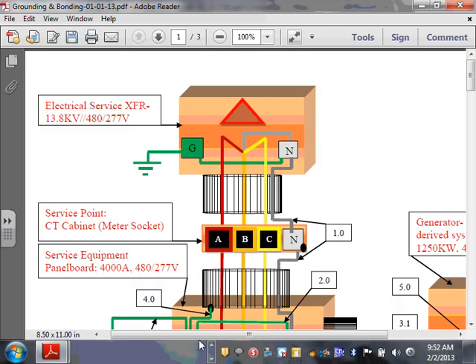So we take the calculation for the building and we call it architectural, not even engineering, load calculation. We call it architectural load calculation. And then you apply, like I said, a demand factor of 50 to 70 based on the type, hospital, whatever, and based on the statistical value that you do, and you size your transformers. And they're absolutely right, guys. You go into a switch gear that you size 4,000 amp, and when everything is humming and up and running, you look at the switch gear and it's pulling 2,000 amp, right? Has anybody who sized a 4,000 amp switch gear gone there and found 4,000 amp pulled out of this system?